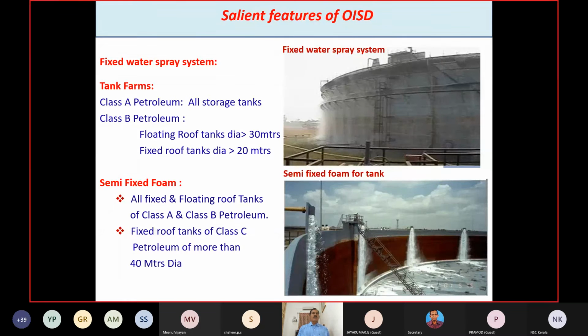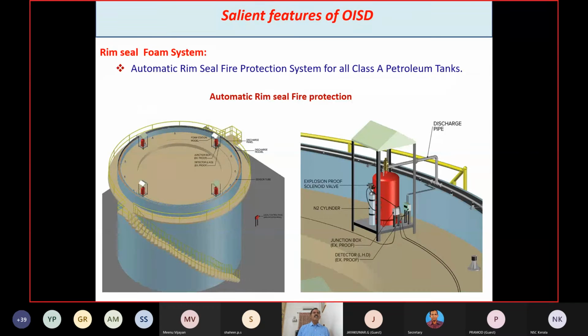And semi-fixed foam: for all fixed and floating roof tanks of Class A and Class B petroleum, we should provide a semi-fixed foam system. And for fixed roof tanks of Class C petroleum of more than 40 meters diameter, we should also provide a semi-fixed foam system. And the rim seal foam system: an automatic rim seal fire protection system for all Class A petroleum tanks, that is floating roof tanks.